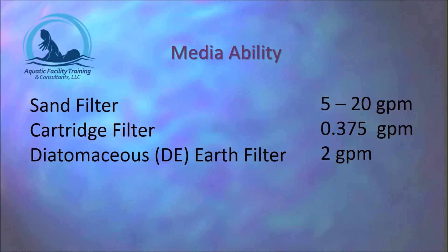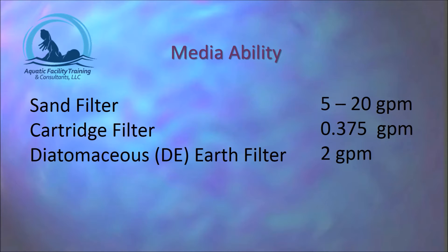Media ability is the amount of water a filter can handle per square foot of filter area, depending upon the exact media that is used. A sand filter has a media ability of 5 to 20 gallons per minute per square foot of filter area. A cartridge filter has a media ability of 0.375 gallons per minute per square foot. A diatomaceous earth filter, or DE filter, has a media ability of 2 gallons per minute per square foot of filter area.